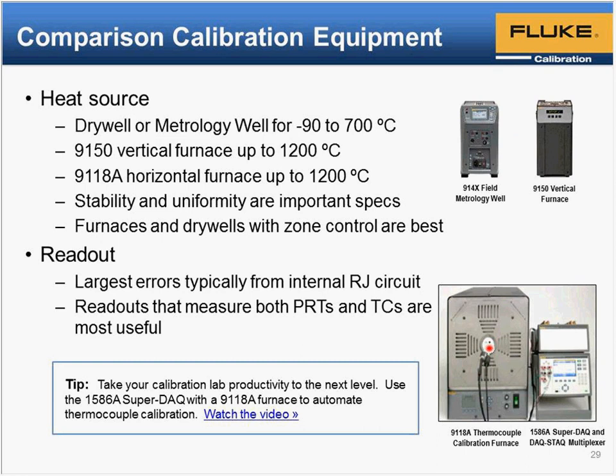The two specifications to consider for the heat source are temperature stability and uniformity. Temperature stability describes how well the furnace can maintain a temperature set point. Is it going up and down in temperature as you're trying to measure, or is it nice and stable? And uniformity describes how consistent the temperature is throughout the furnace. Does the furnace have large temperature gradients throughout the working area of the furnace, or small temperature gradients?